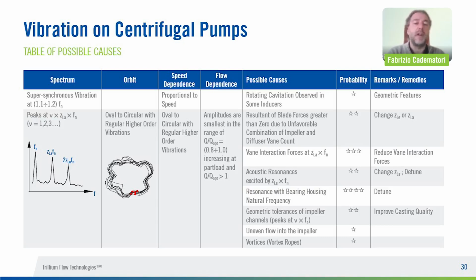Okay, our journey now arrives at blade pass frequency. If the spectrum shows peaks at rotating speed and harmonics of blade pass frequency, that is the rotating shaft frequency multiplied by the number of impeller blades, and the orbit looks like a flower, a daisy for example, with as many petals as there are blades in the impeller, then a periodic force generated by hydraulic interaction between rotor and stator is active. With an unfavorable combination of impeller and diffuser vane count, or acoustic resonance with blade pass, or mechanical resonance of the bearing support, we can see orbit and spectrum similar to those in the picture.